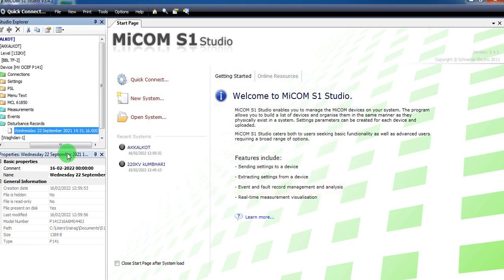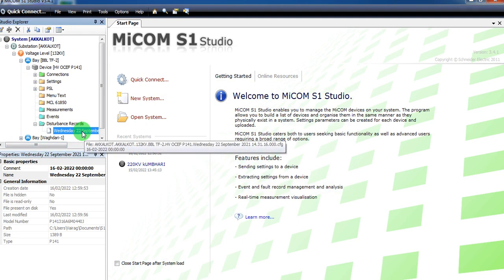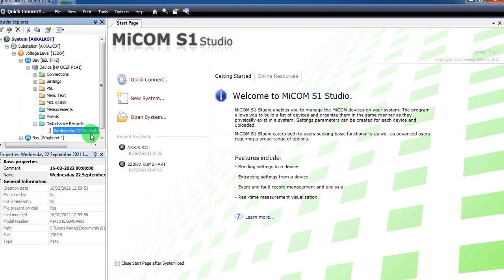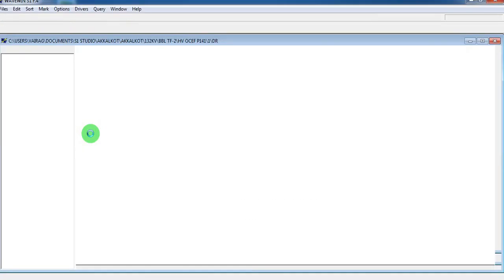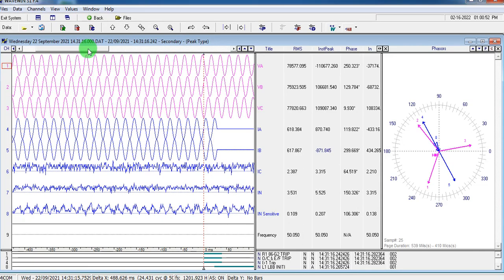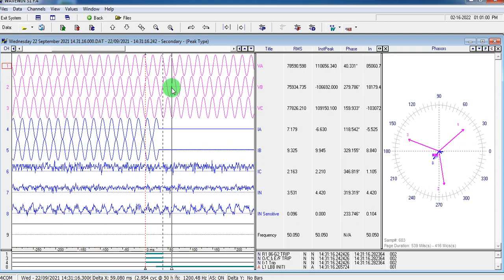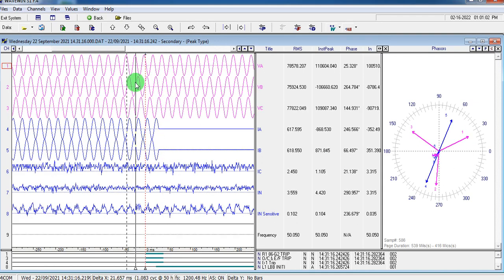Right click and it will open in WaveWin software. The disturbance record gives us a lot of information such as current and voltage values at the time of fault. It also tells us which fault indications, i.e. which fault parameters became active during the fault.